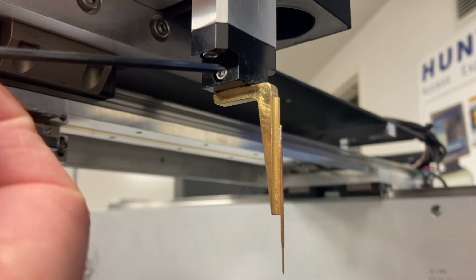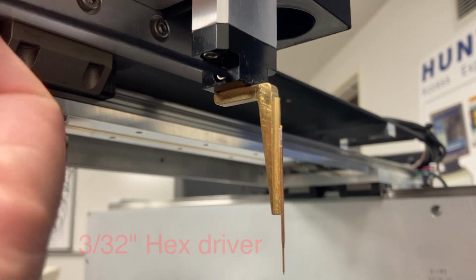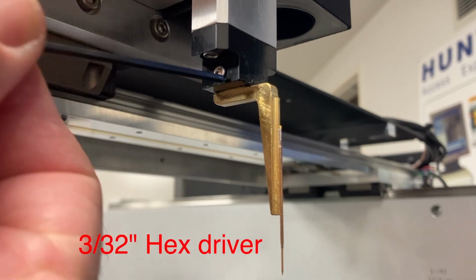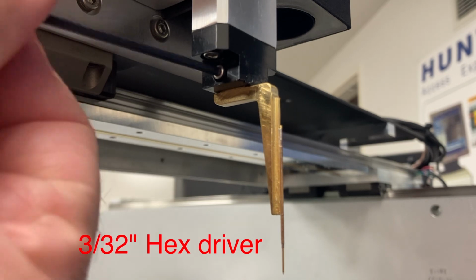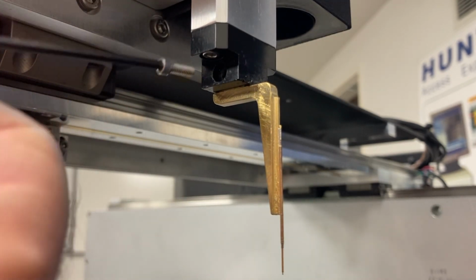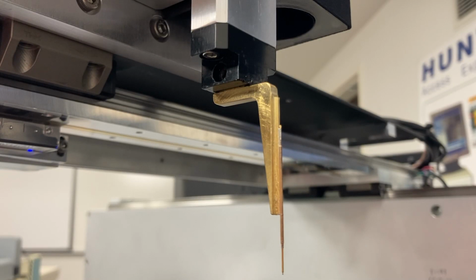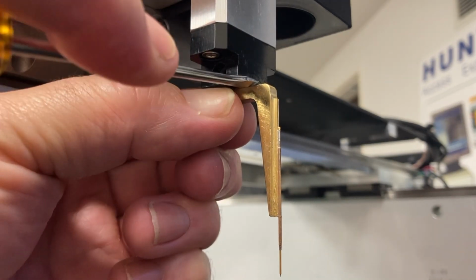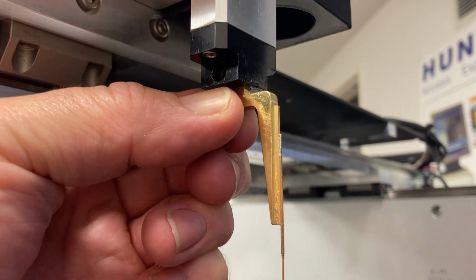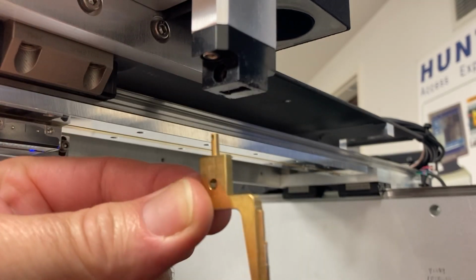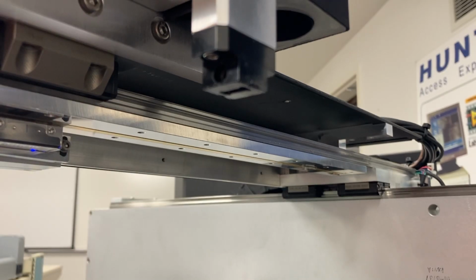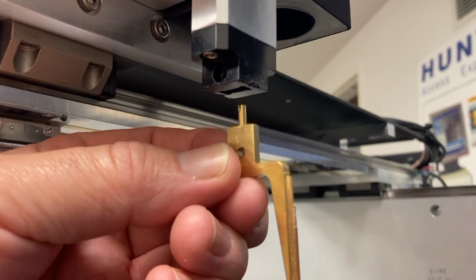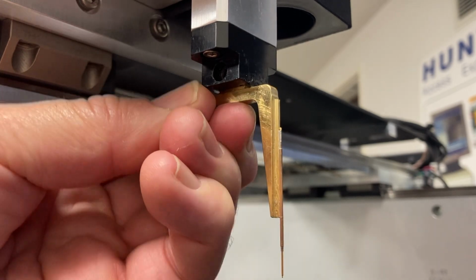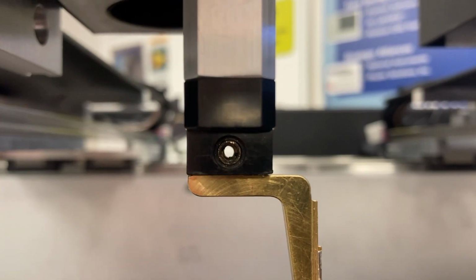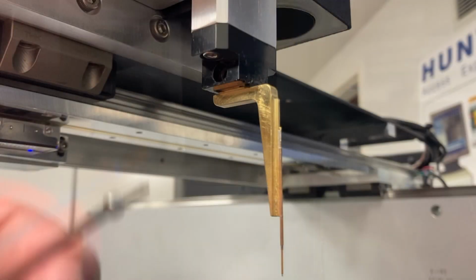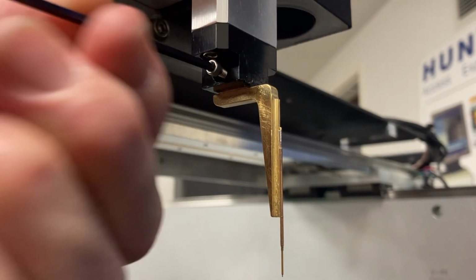To replace a probe plate, simply remove the screw that goes into the front of the probe holder. Once the screw is removed, you simply need to pull down on the probe plate to remove it. You may need a small screwdriver to pry this probe plate downward a little bit before you can pull it out all the way. To reinstall the probe plate, simply insert it into the probe holder, align the holes between the holder and the probe plate, and then reinsert the screw and tighten it down.